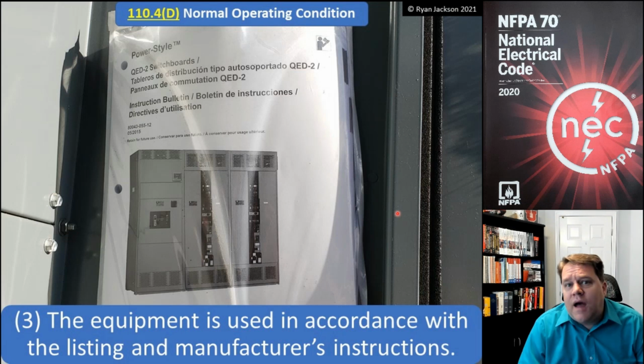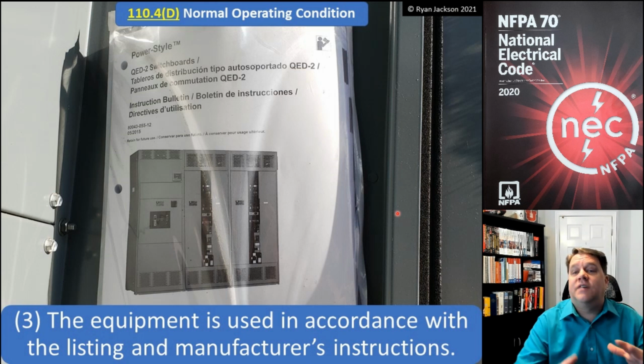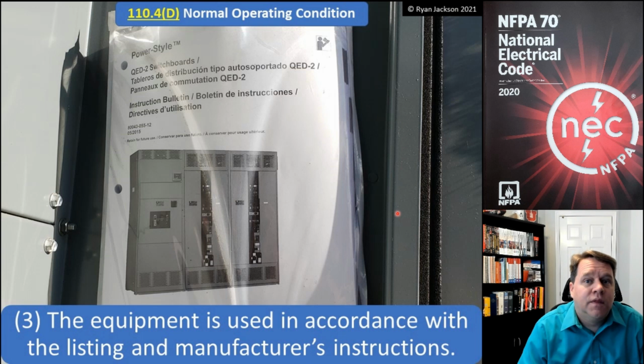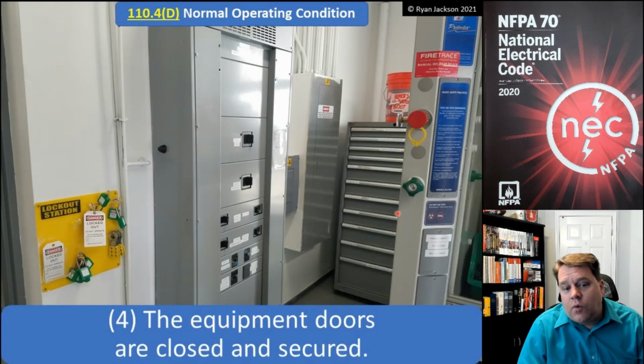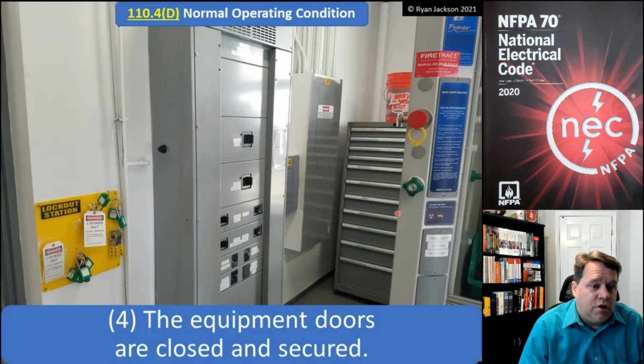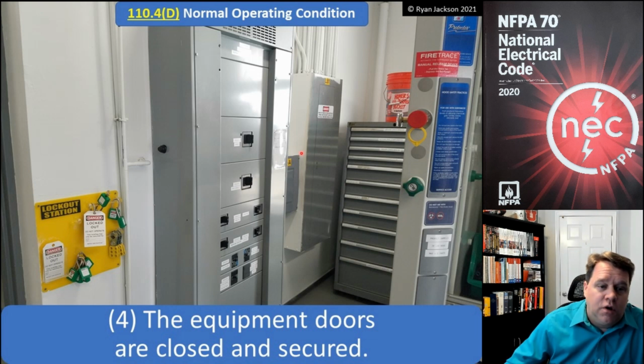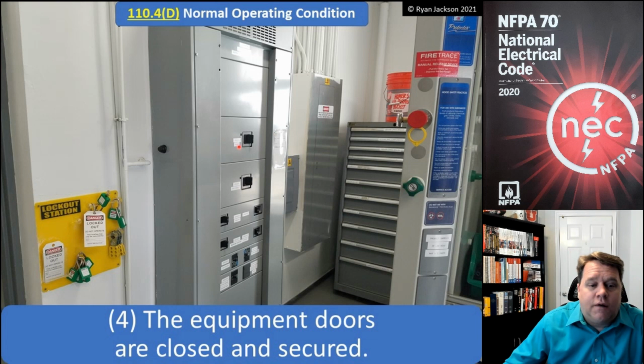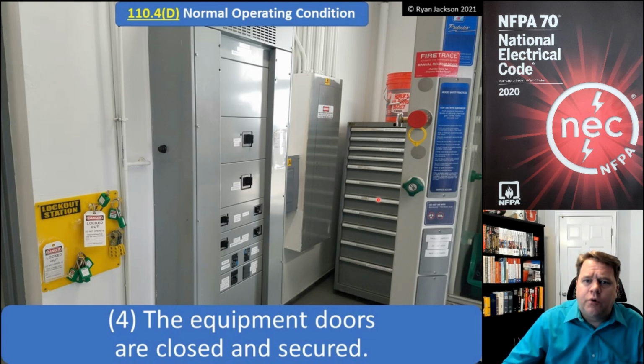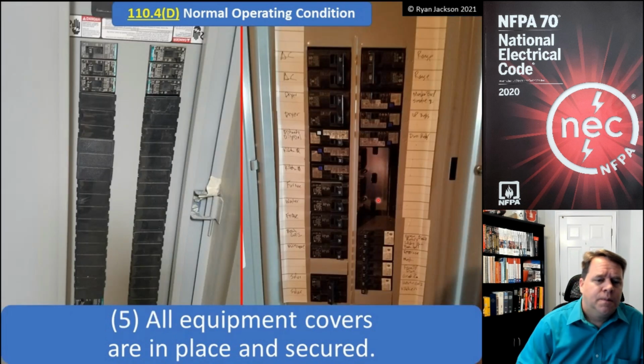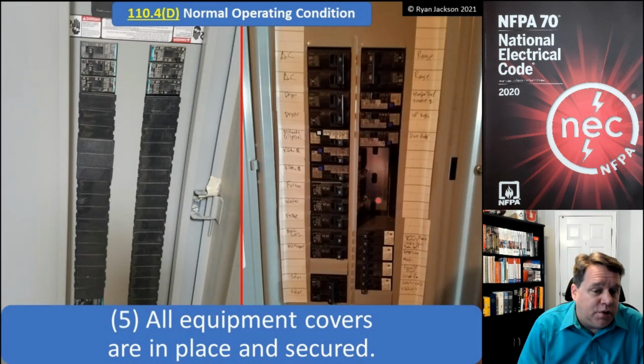The equipment has to be used in accordance with the listing and manufacturer's instructions, so we're going to make sure that the equipment is being used for what it's actually designed to do. We need to make sure that the equipment doors are closed and secured. Looking at this photograph, can I walk up to that panel board and turn on and off the circuit breakers? Sure, it appears so. It looks like that's in a normal operating condition. All equipment covers are in place and secured.